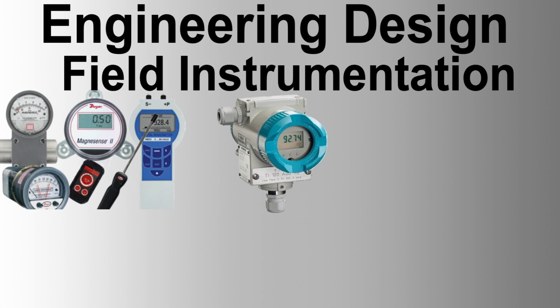Factory acceptance test, FAT. A factory acceptance test, FAT, must be performed on all instruments before shipment to verify their performance and compliance with the specified requirements. The FAT must include functional testing, calibration, and any other tests necessary to confirm that the instruments meet the performance standards specified in the datasheets and specifications. FAT reports must be provided to the purchaser for review and approval.